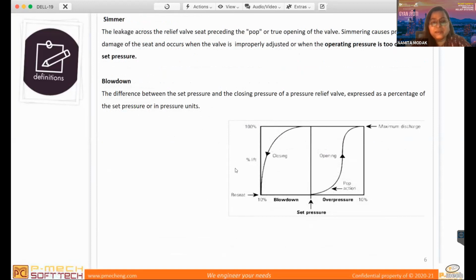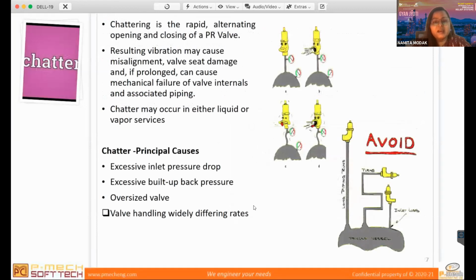As I explained, blowdown is the difference between the PSV opening and closing pressures. Wherever you set the pressure, it doesn't happen that once it has relieved, it closes exactly at that set pressure. So the difference between the opening and closing pressure is called blowdown. Now chattering. Chattering is a very famous phenomenon in industry. Chattering happens due to three causes. First is excessive inlet pressure drop. If you see this case, there are multiple loops in the inlet of your PSVs, so a lot of pressure drop is happening at the PSV inlet. Normally API 520 does not allow more than 3% of your set pressure. But if there is still an excessive inlet pressure drop, chattering can occur. So what is chattering? It's an on-off of your PSV. I mean, your PSV keeps on opening and closing. That's called chattering.